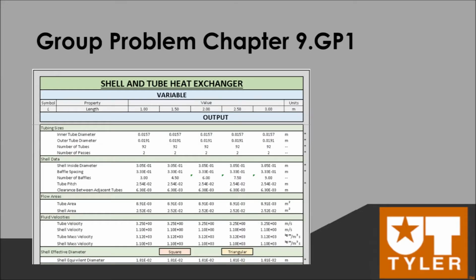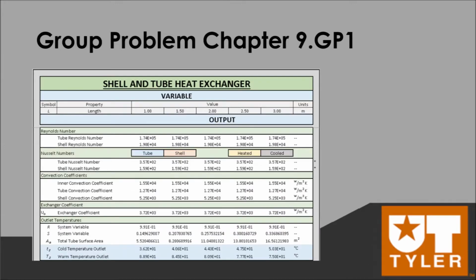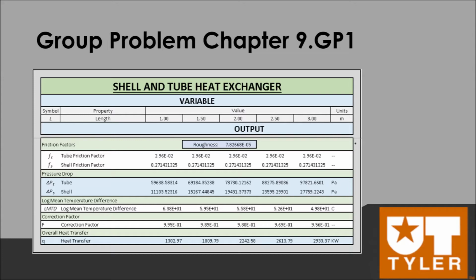A Microsoft Excel calculator was generated to determine the properties of the shell and tube heat exchanger. The detailed step-by-step analysis can be found on pages 466 to 471 in Janna's book Design of Fluid Thermal Systems, 4th edition. The assumptions made for the calculations were steady-state conditions, adiabatic heat exchanger, no fouling factors, along a streamline, incompressible fluid, inviscid fluid, and hot fluid in the tubes. The properties for each fluid were evaluated at inlet temperatures.